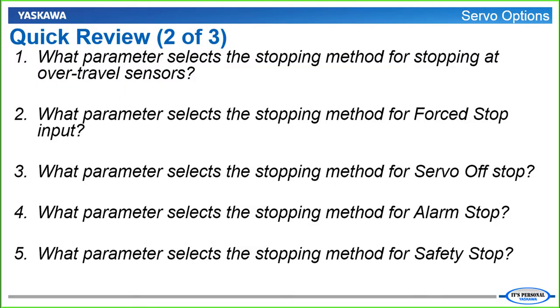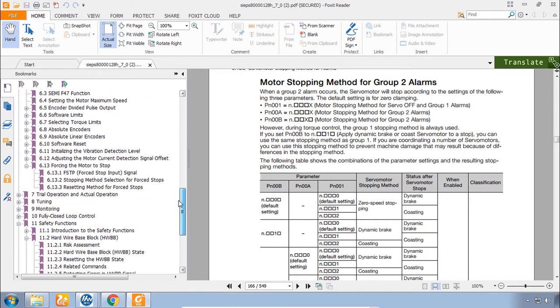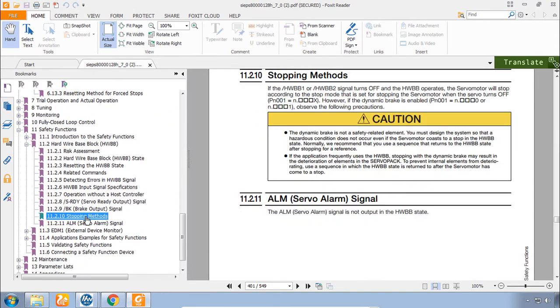And looking ahead to the next question. You see that group one alarms also PN001. But scrolling down. Group number two also involves PN00A and PN00B. That was question number four. Number five. Stopping method for safety stop. Safety stop is by itself in chapter 11. And the stopping method parameter was again PN001.